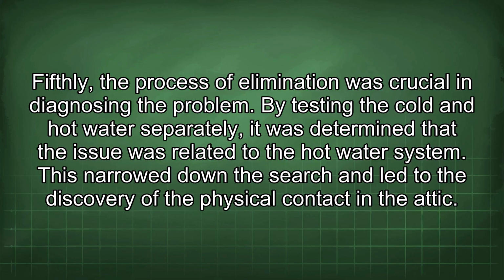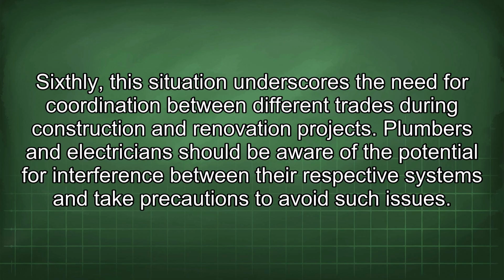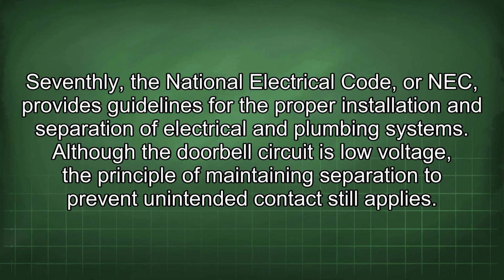Fifthly, the process of elimination was crucial in diagnosing the problem. By testing the cold and hot water separately, it was determined that the issue was related to the hot water system. This narrowed down the search and led to the discovery of the physical contact in the attic. Sixthly, this situation underscores the need for coordination between different trades during construction and renovation projects. Plumbers and electricians should be aware of the potential for interference between their respective systems and take precautions to avoid such issues. Seventhly, the National Electrical Code, or NEC, provides guidelines for the proper installation and separation of electrical and plumbing systems. Although the doorbell circuit is low voltage, the principle of maintaining separation to prevent unintended contact still applies.